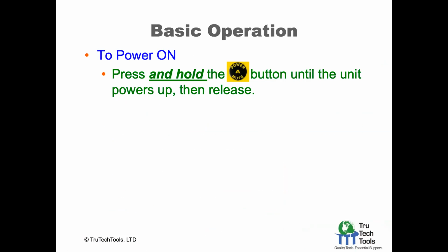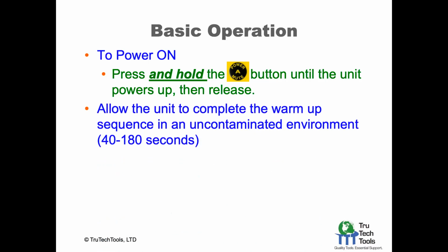So of course, to power it on, you hit the power button. We talked about these buttons having multiple purposes on them. You need to press and hold to get it to power on. And then once the unit powers up, you hear power up, you can release the button. You want to allow the unit to completely warm up in an uncontaminated environment in order to get its baseline. This is sort of like calibrating your carbon monoxide meter before you do a test. And in this case, it automatically moves through and decides when it's done. So it can be anywhere from 40 to 180 seconds. I think generally it's dependent upon the temperature of the unit.